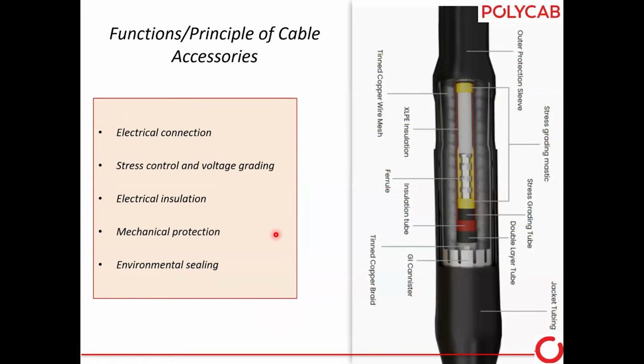So let's see the first joints. There are different components required for making the joints, and each component has its own function, but I have broadly classified these under 5: electrical connections, stress control and voltage grading, electrical insulation, mechanical protection, and environmental sealing. For the electrical connection, we use ferrules. For stress control, we use the semiconducting tubes. So let's see them one by one.